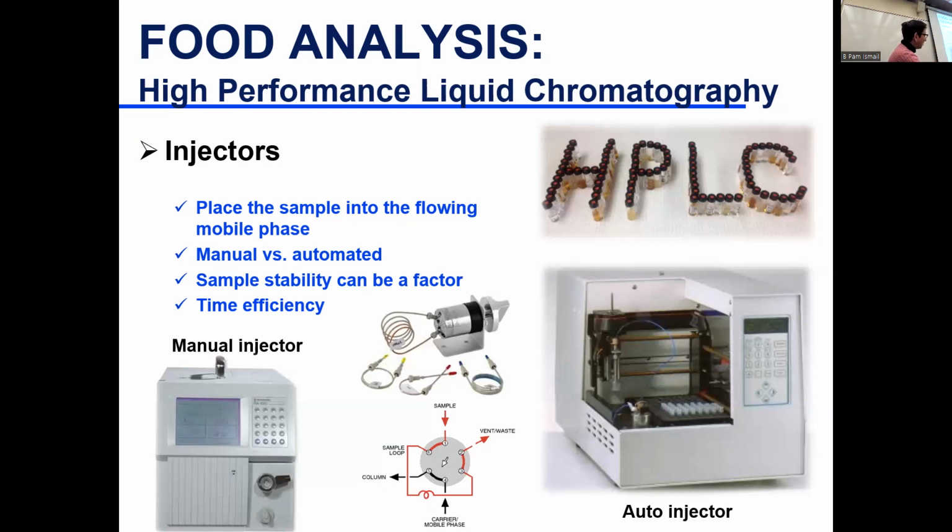And then you all saw the automation of the needle coming in and penetrating the septa in the cap of those little vials, going in and automatically taking out 20 microliters. And we heard these sounds of opening valves and closing valves. So basically, when the sample is injected, we hear valves opening, allowing the mobile phase to go through your sample loop to carry the sample. Otherwise, valves are closed and the mobile phase bypasses the sample loop.